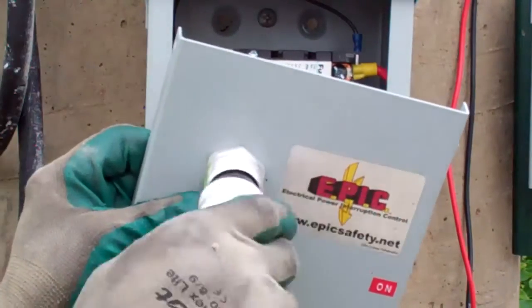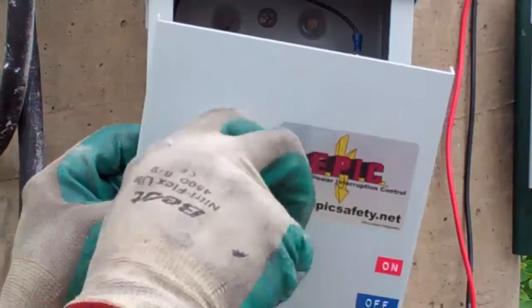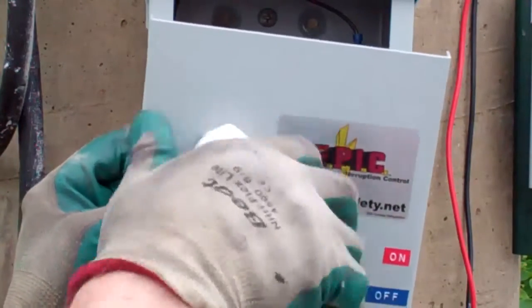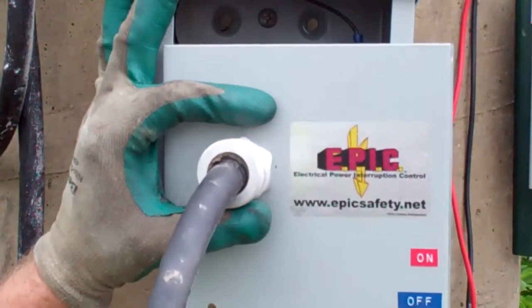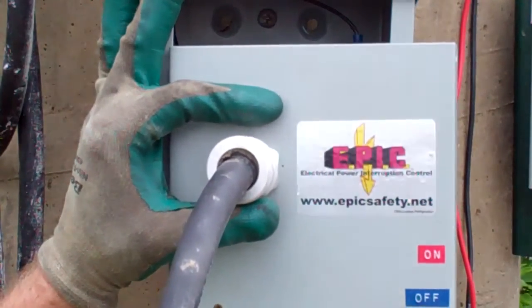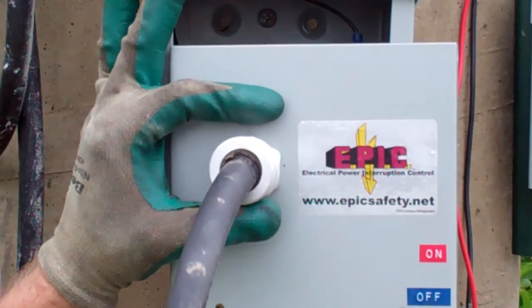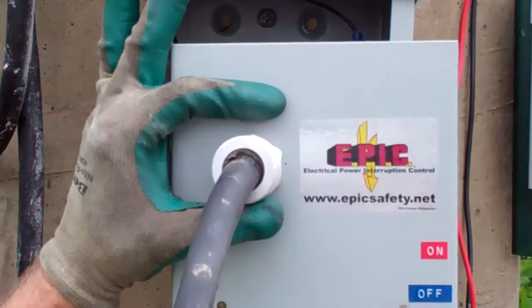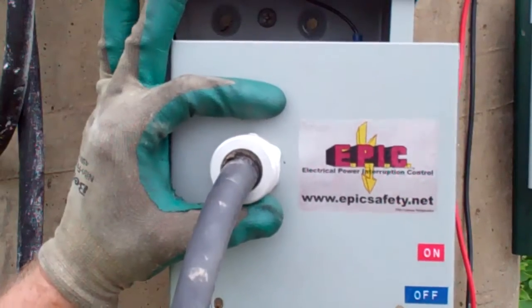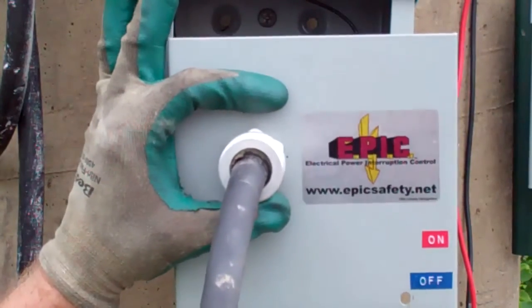We'll adjust the rubber grommet up to the top and tighten it down. There's been some testing done on how tight you should tighten that nut. It's 3 turns from the time the threads engage. If you go too tight, the cord won't pull out. If you go too loose, water will get in. So 3 full turns.